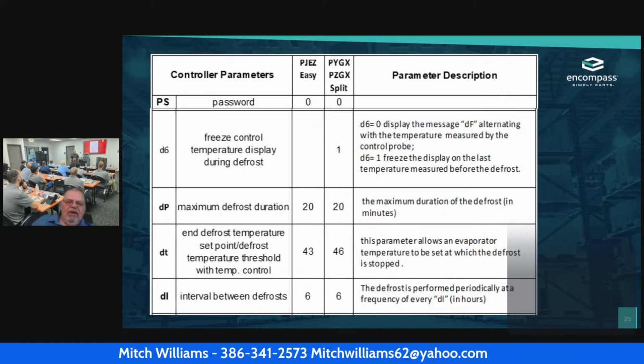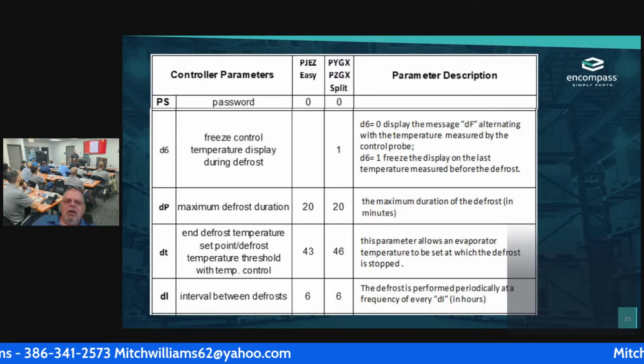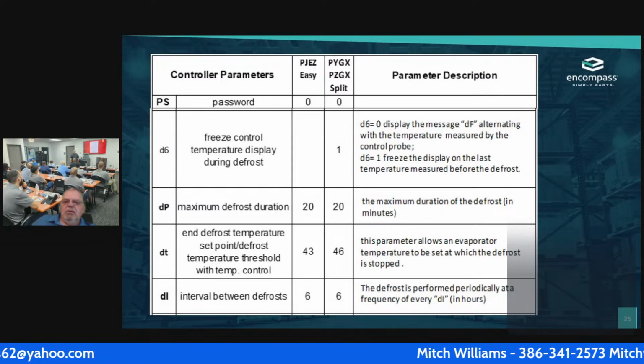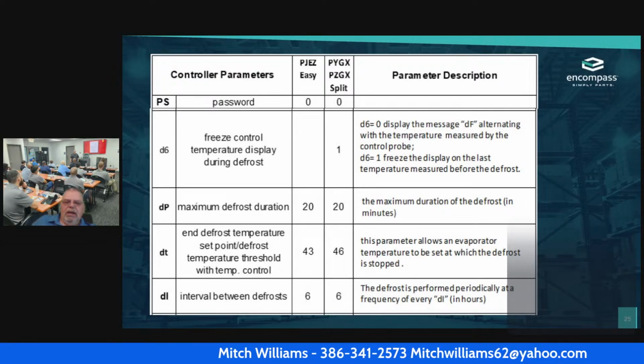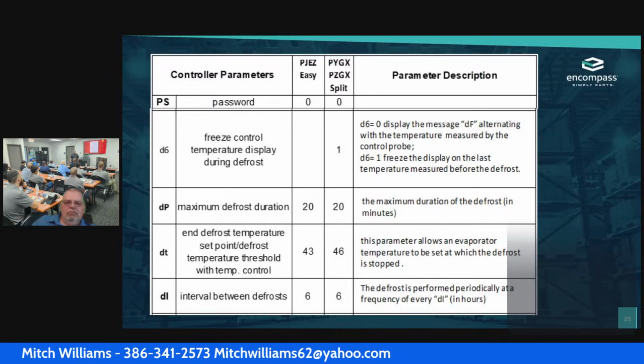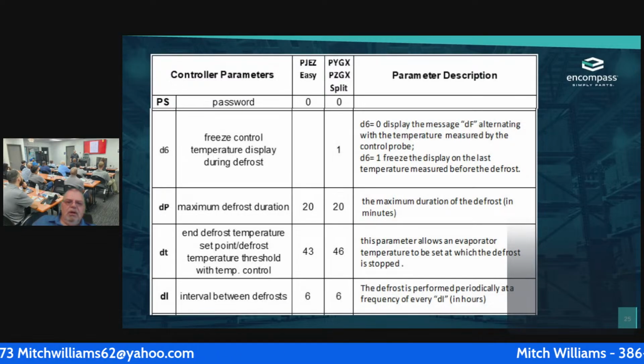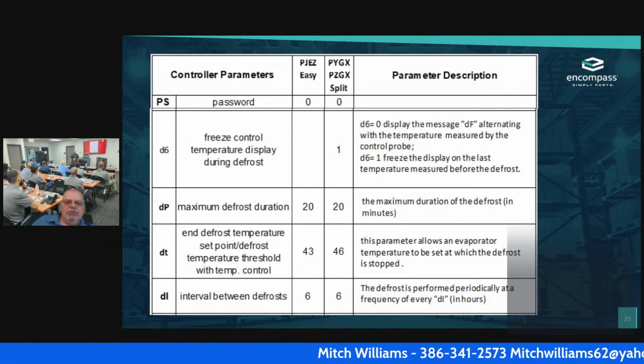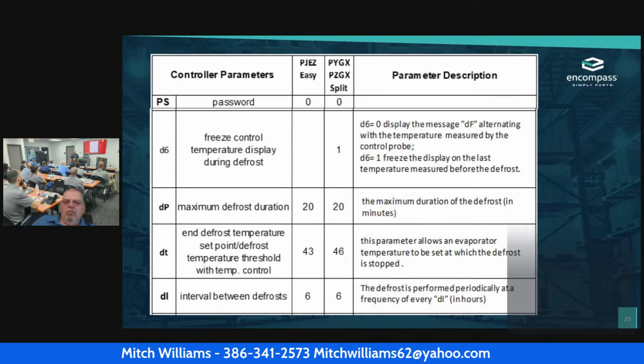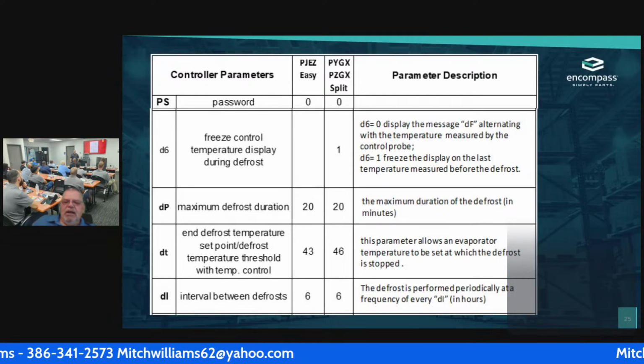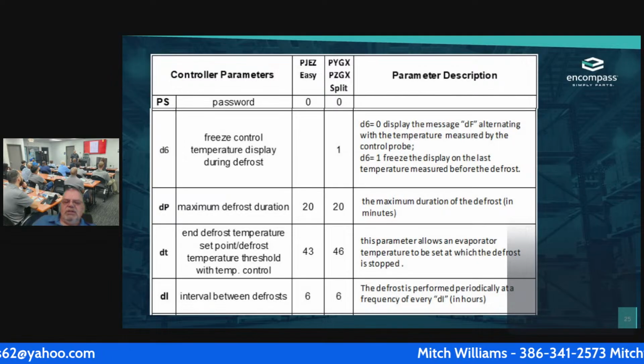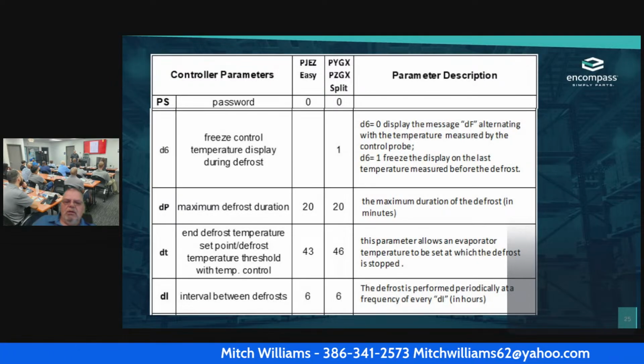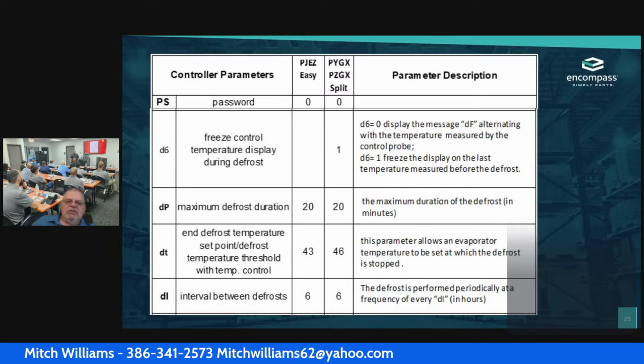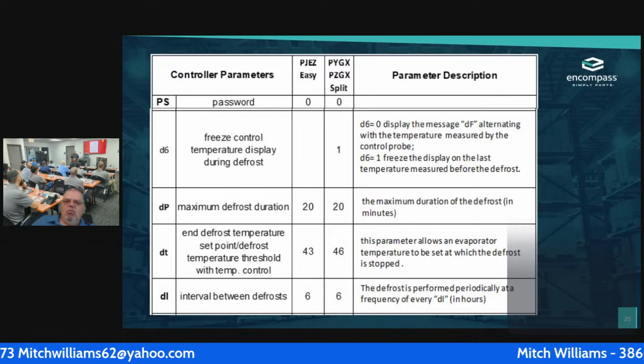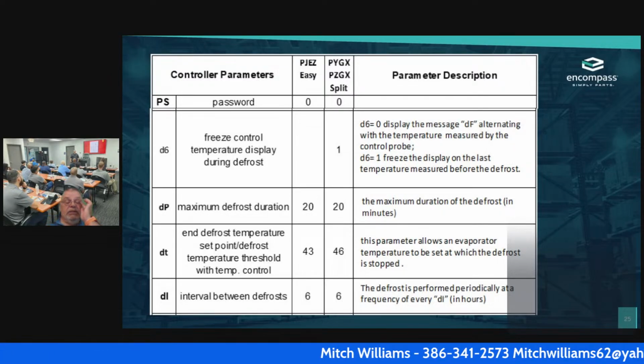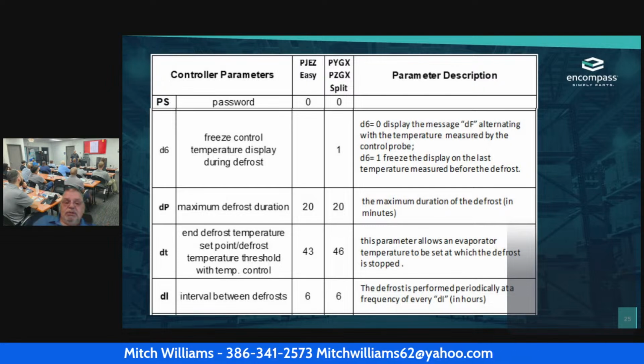Okay. Now once I go through and I scroll, the next one is DP, my maximum defrost duration. The maximum duration of the defrost in minutes is 20. Okay. I can shorten it, so I can go in and change that if I want to. If I have a DT, that ends the defrost temperature set point, the temperature threshold with the temperature control. This parameter allows an evaporator temperature to be set in which the defrost stops. So if I've got the unit on the PJEZ, that is set to 43 degrees. If it's the PYGX or the PZGX, it's set to 46. So I can go in and adjust those temperatures also.